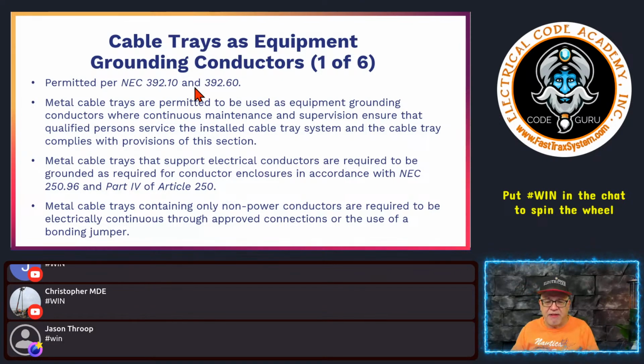UL 1685 method 1 for flame propagation. It's met that in single insulated conductors and single conductor cables, 1/0 and larger, for the ungrounded and grounded conductors. Equipment grounds that get installed in cable trays can go down as small as a 4 gauge, and they do not have to be CT use marked, because equipment grounds could be bare or insulated. That's a lot of info in short, but go back and watch that episode. When it comes to cable trays, you'll get a lot out of it.